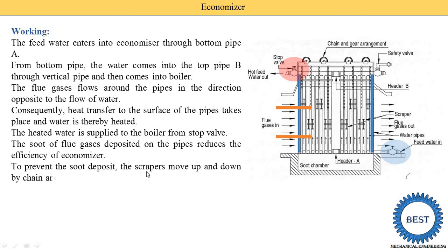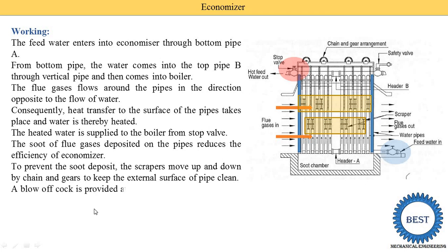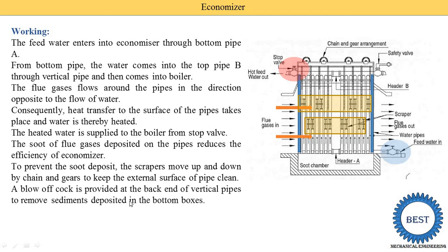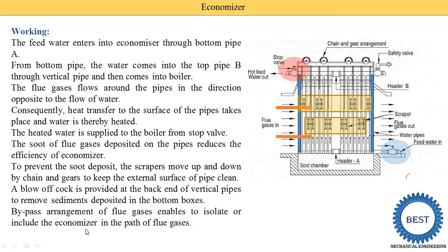The soot of the flue gases deposited on the pipe reduces the efficiency of the economizer, because soot sticking on the pipe reduces the heat transfer coefficient. That is why scrapers are installed. To prevent soot deposit, the scrapers are moved up and down by the chain and gear arrangement, removing the soot from the pipes. A blow-off cock is provided at the back of the vertical pipe to remove sediment deposited in the bottom box and to empty the economizer. A bypass arrangement for the flue gases enables isolating or including the economizer, allowing control of the amount of flue gases passing through it, with the rest bypassed directly to the chimney.